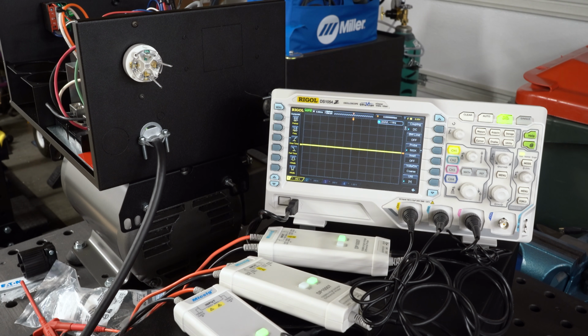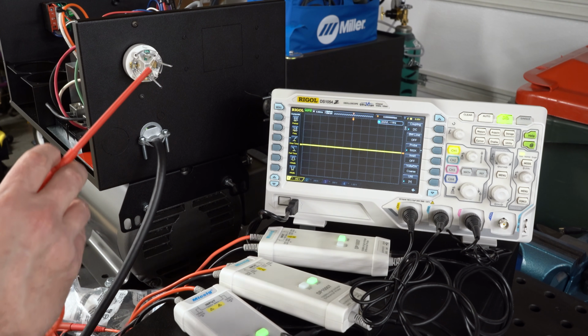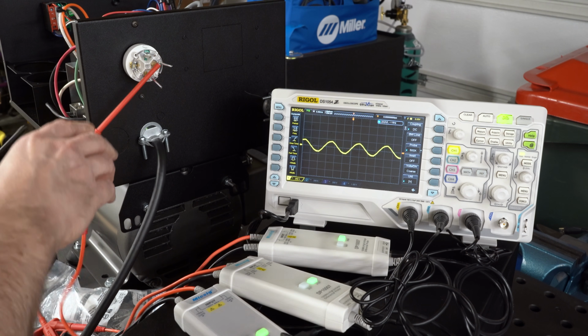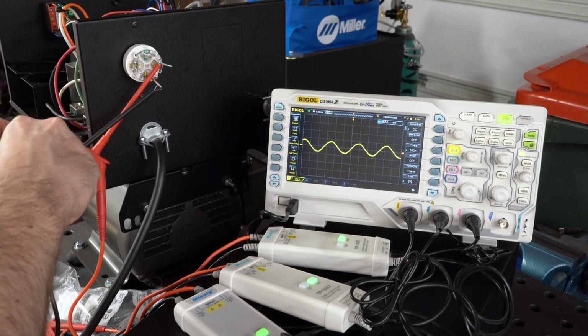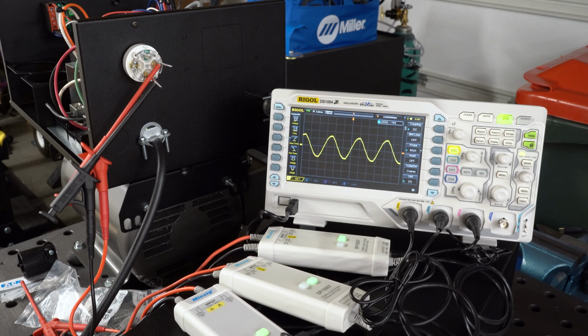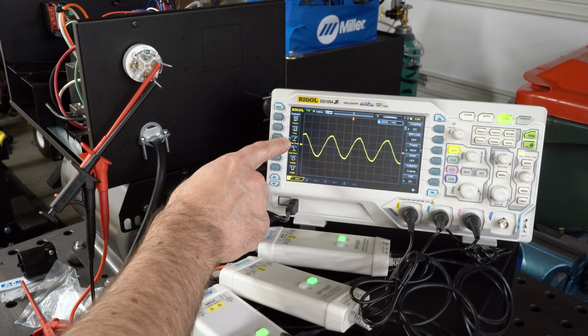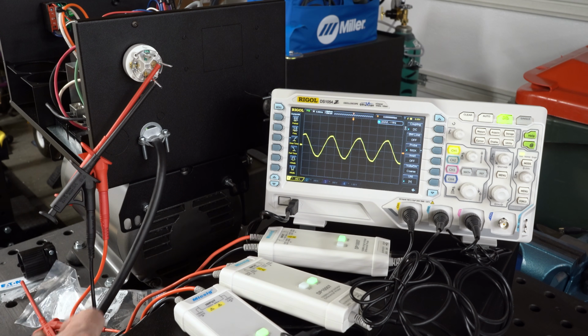Let's start by just taking one of these probes and measuring across the 240 volt input. Now I have this plugged in, and even though the phase converter is off, the input 240 volts is passed through. And you can see, we put the probe on it, we're seeing a nice 240 volt RMS waveform. This is exactly what one would expect.